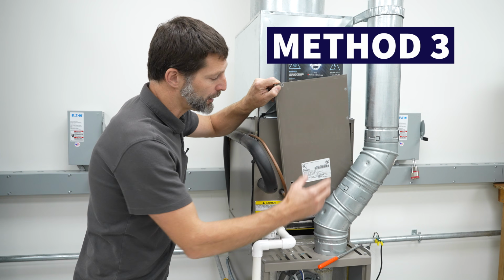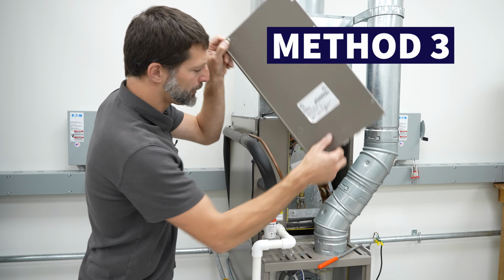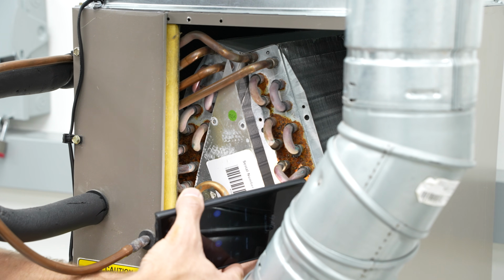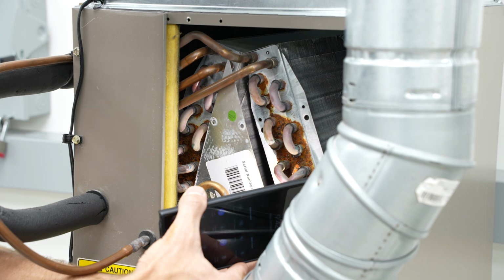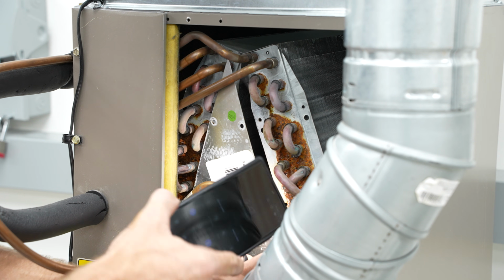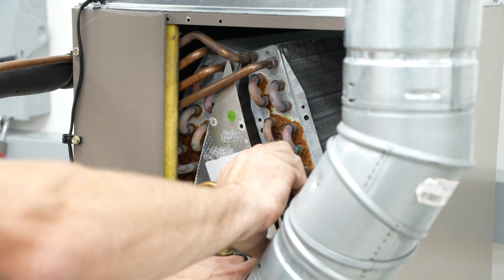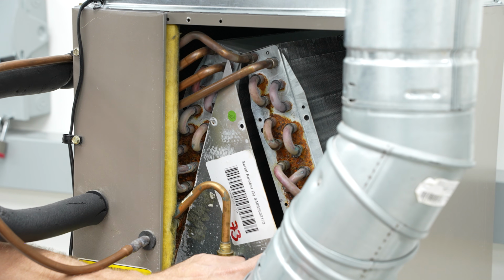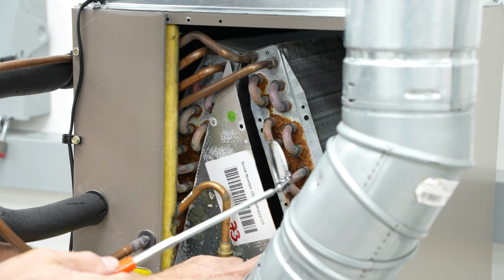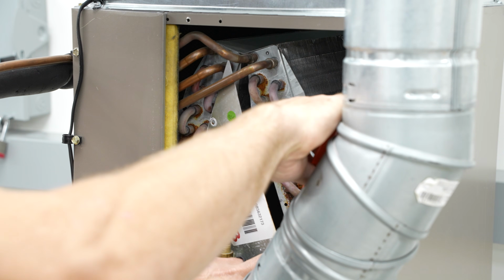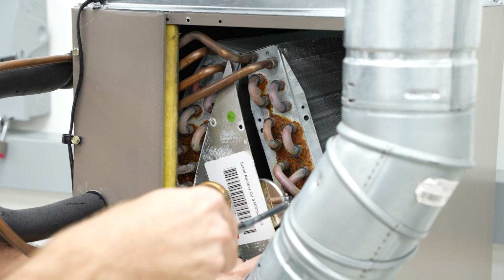Method number 3 involves removing the front cover of the evaporator coil and then removing the screws on the little A plate in order to visually inspect on the inside. So you could remove this plate completely or just pull it back, and so you can see this side here, and then on the other side you can take a picture with your phone, or you can take a mirror with another flashlight in order to visually inspect this side. It's definitely harder with a mirror.